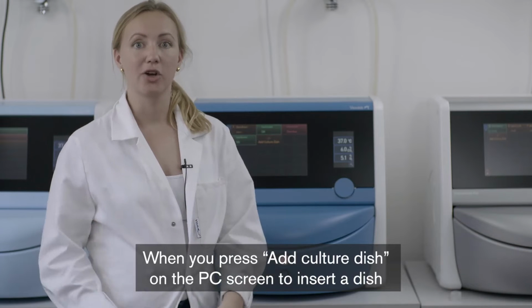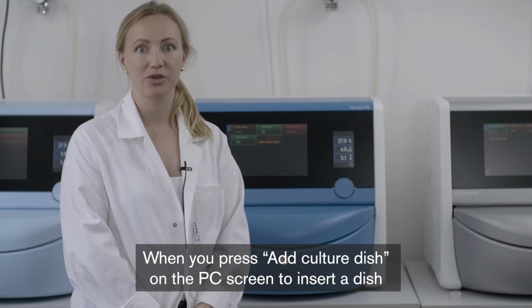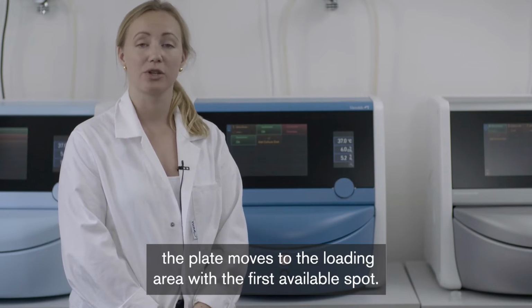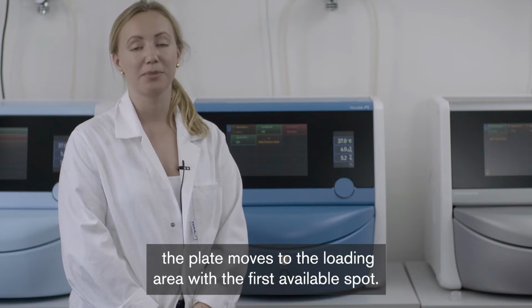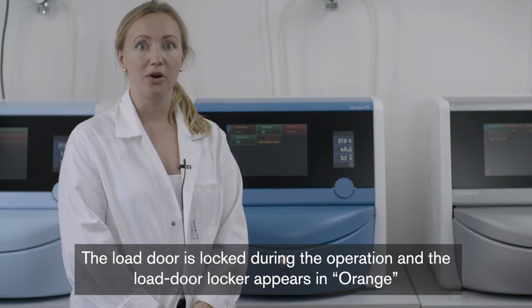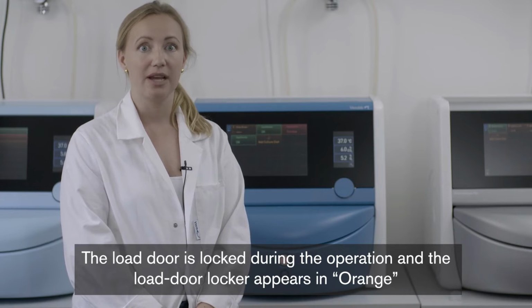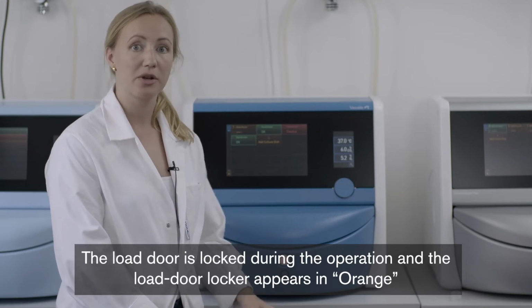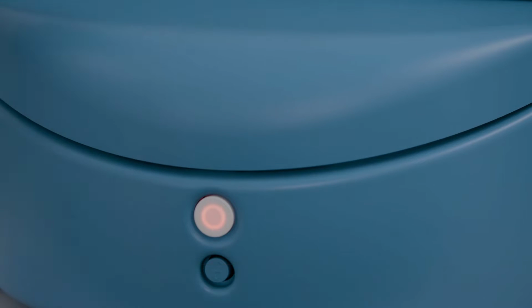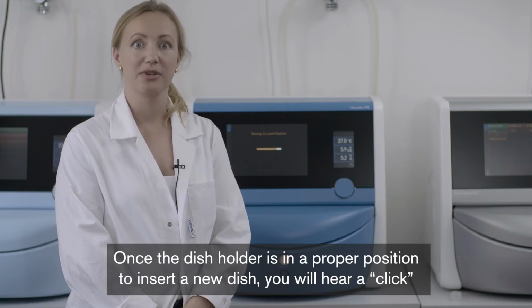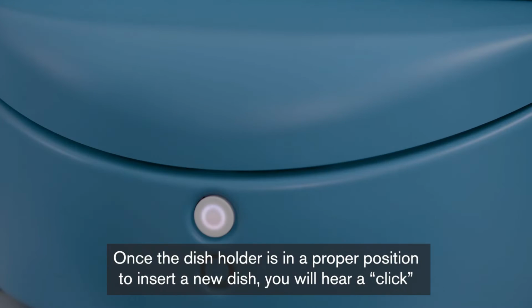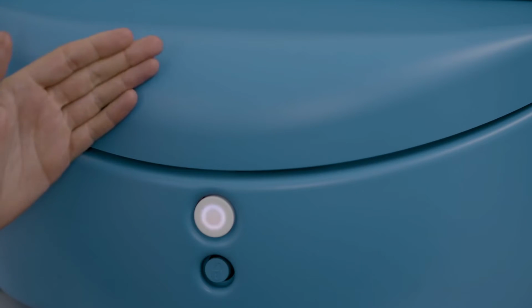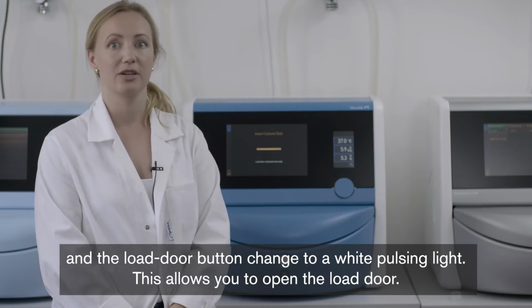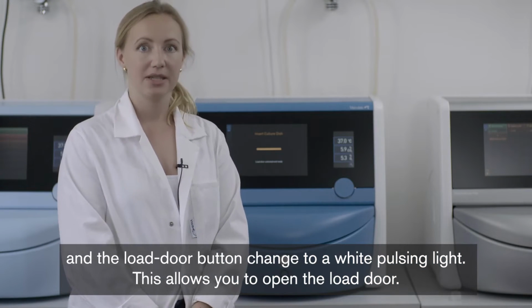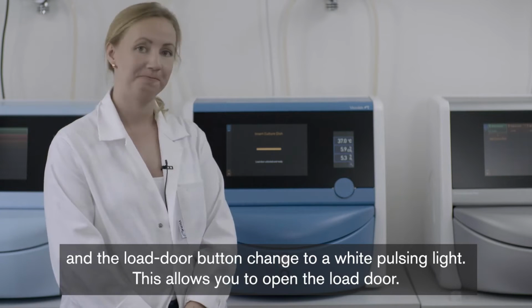When you press Add Culture Dish on the PC screen to insert a dish, the plate moves to the loading area with the first available spot. The load door is locked during the operation, and the load door locker appears in orange, and you won't be able to open it. Once the dish holder is in proper position to insert the new dish, you will hear a click, and the load door button changes to white pulsing light. This allows you to open the load door.